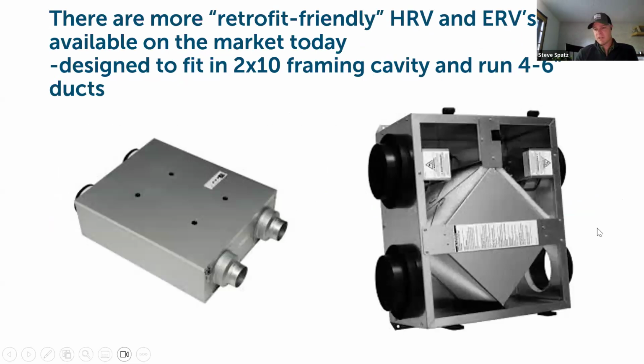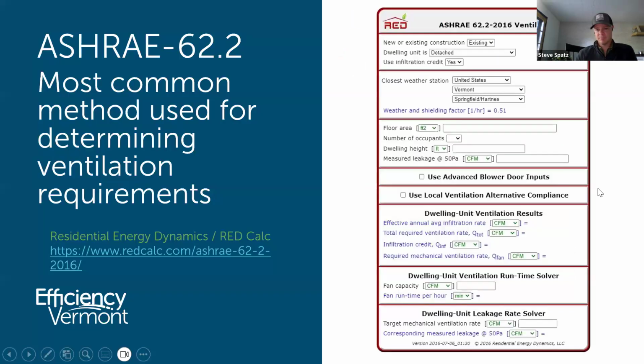When we're talking about retrofit applications, there are quite a few products in the market that are designed around retrofit, meaning that they are small cabinet assemblies that can be fit into existing framing cavities and utilize smaller diameter ductwork. So you have a little bit more flexibility of running the ducts to these systems and getting these systems installed in existing cavities where you're not specifically designing around the needs of the duct system and/or the equipment to fit into the building. So, a lot of options for equipment on the market, is another note.